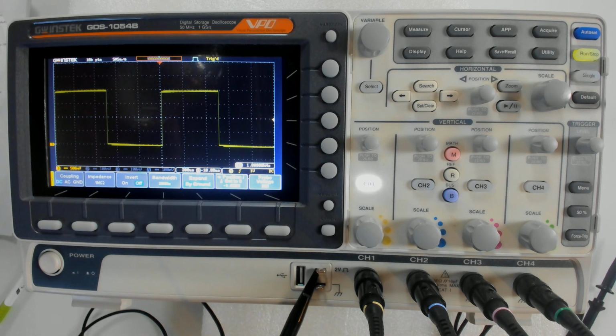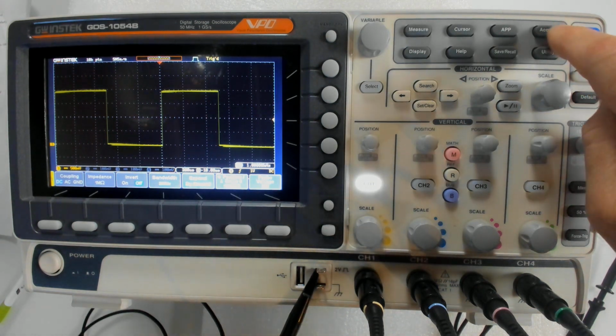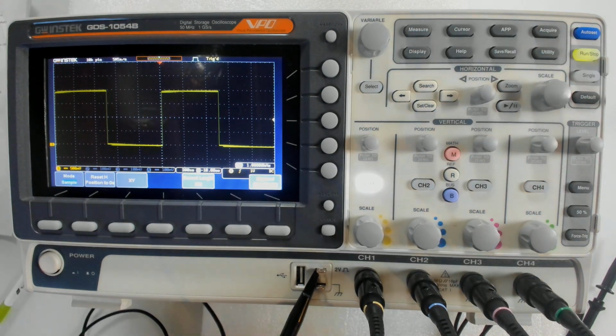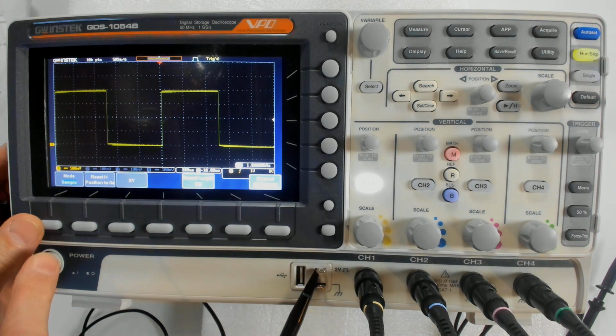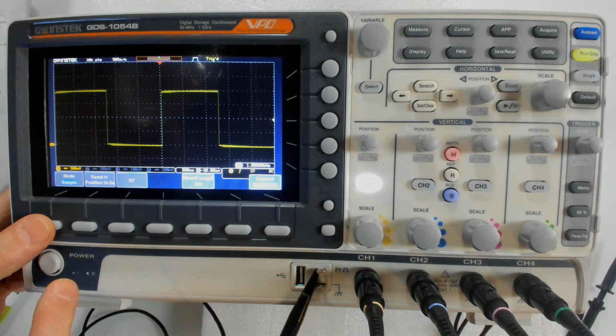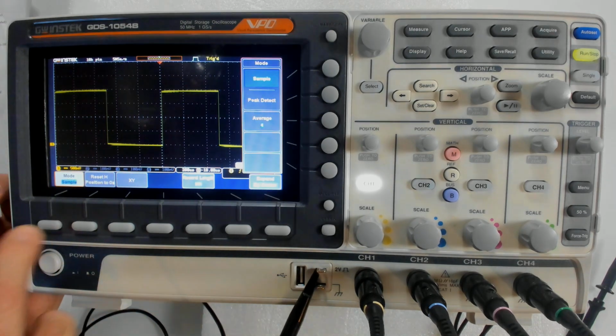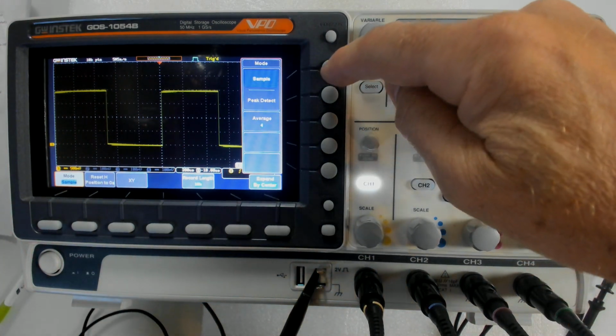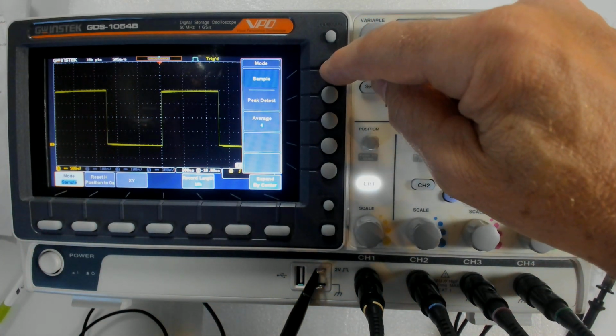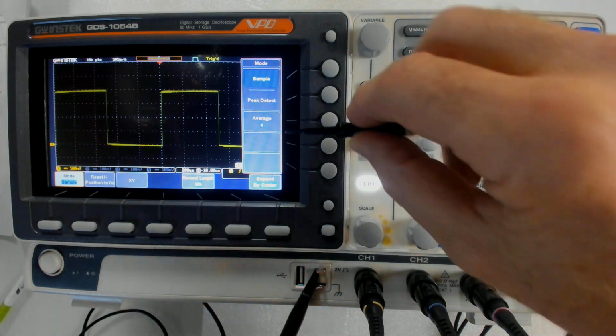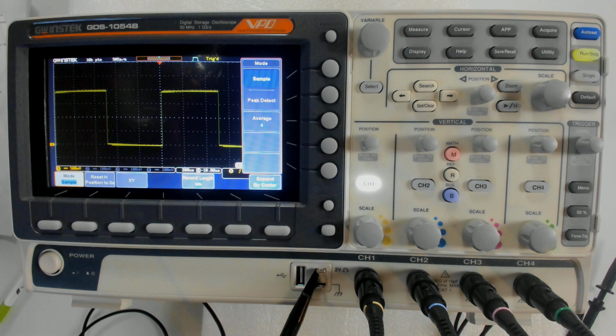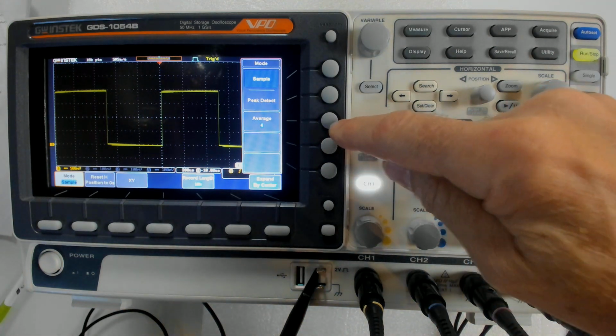Averaging tends to get rid of noise because noise tends to be random. If something is randomly high and low, when you average it all together, the net is 0. That's a trick we use to get rid of noise. That ability is up here at the acquire button. If we push that, it'll bring up a menu where we can pick the mode. Let's see where that takes me. Okay, so I can either read every sample as it comes into the scope, or I can choose to average 4 readings together. And that should clean up the signal.